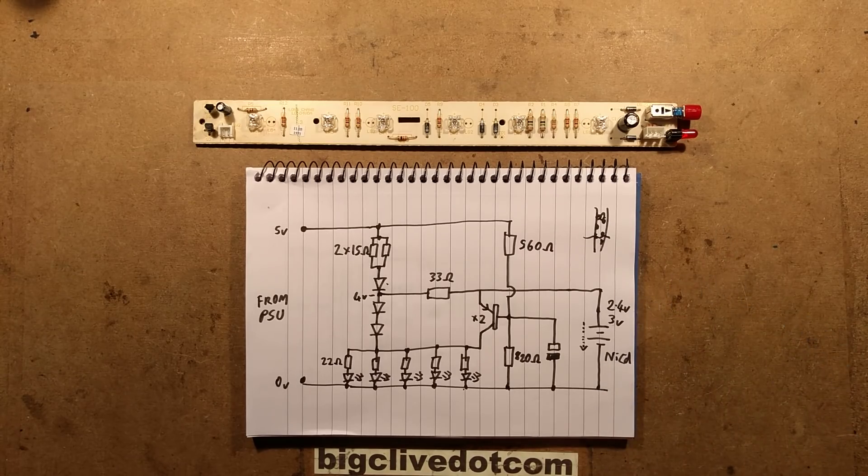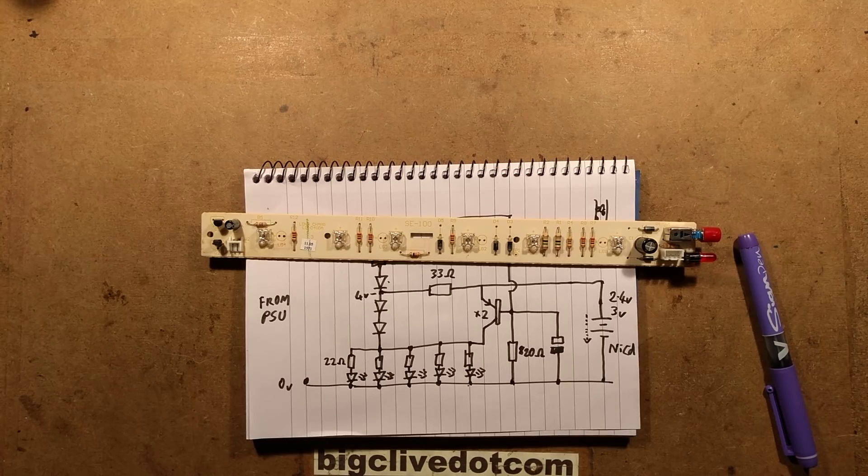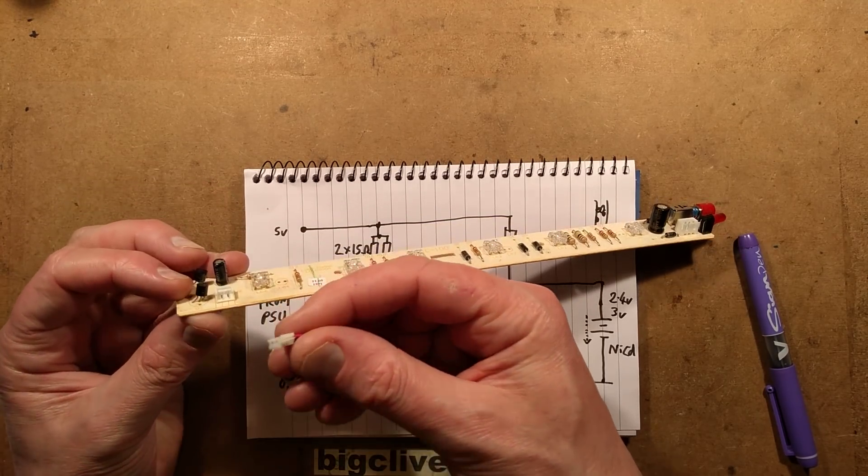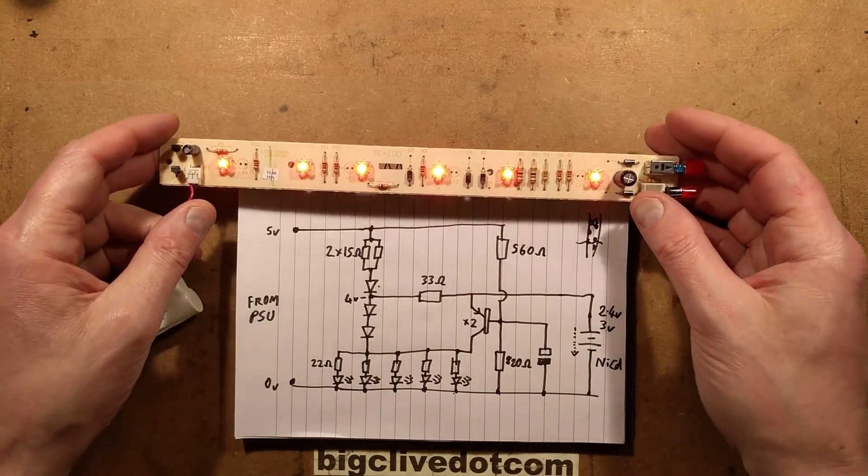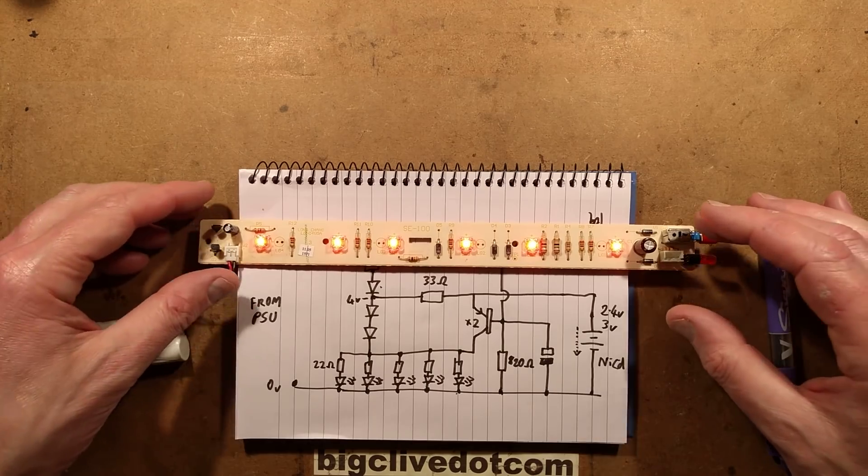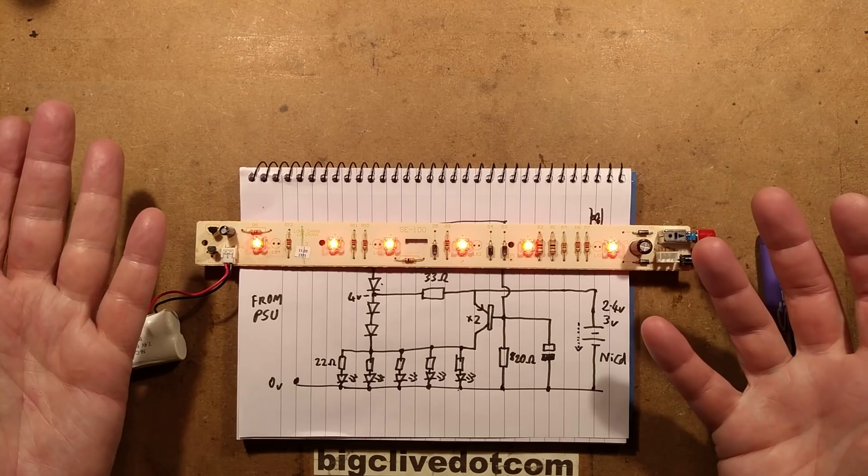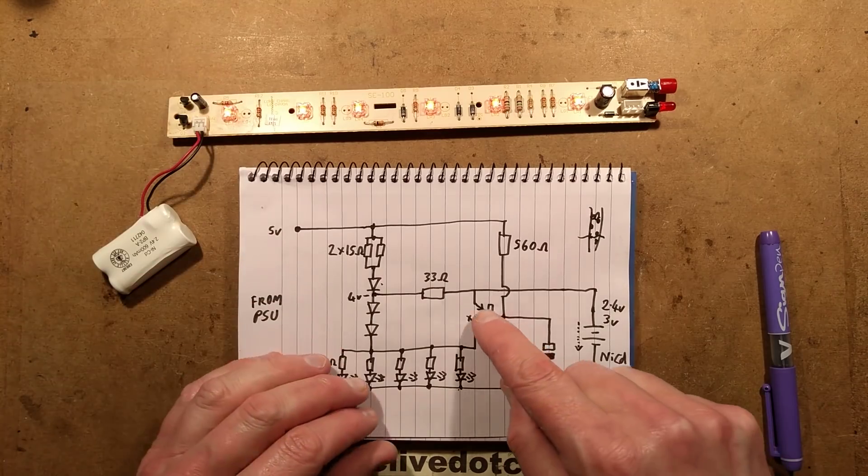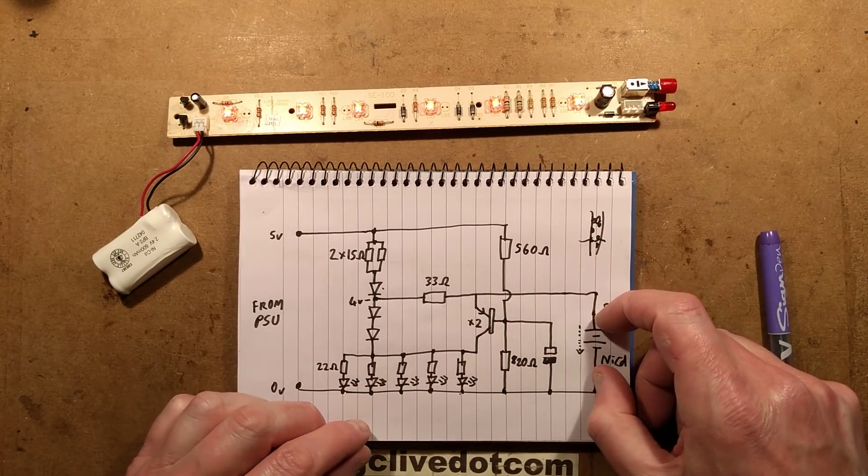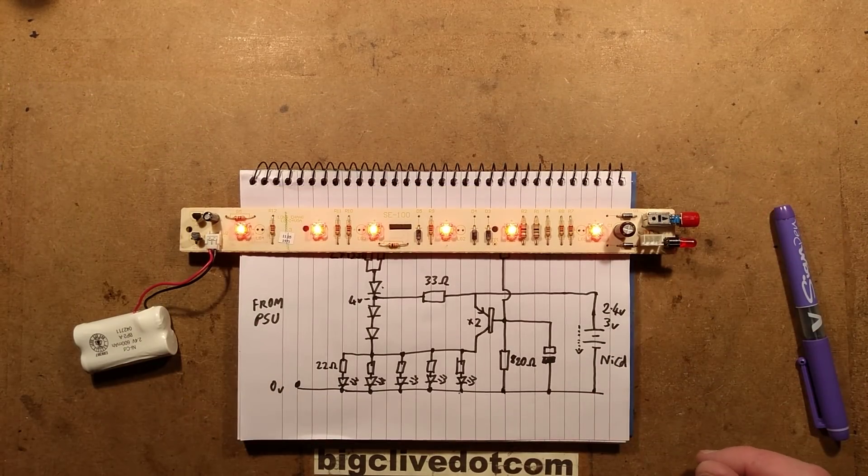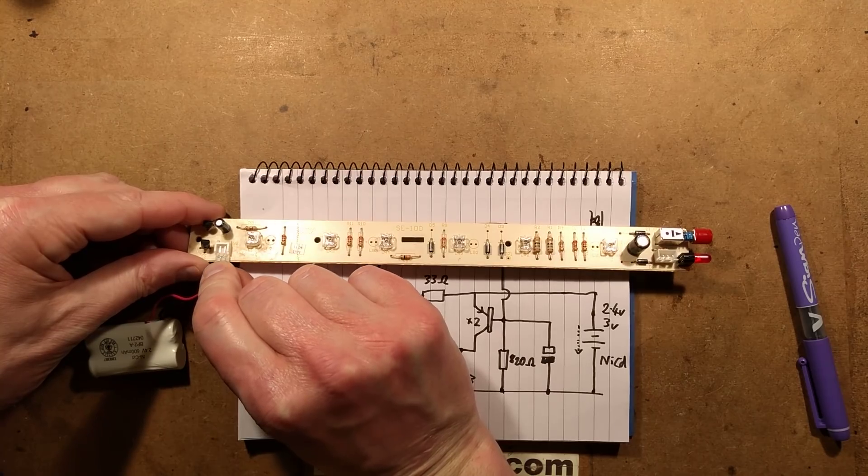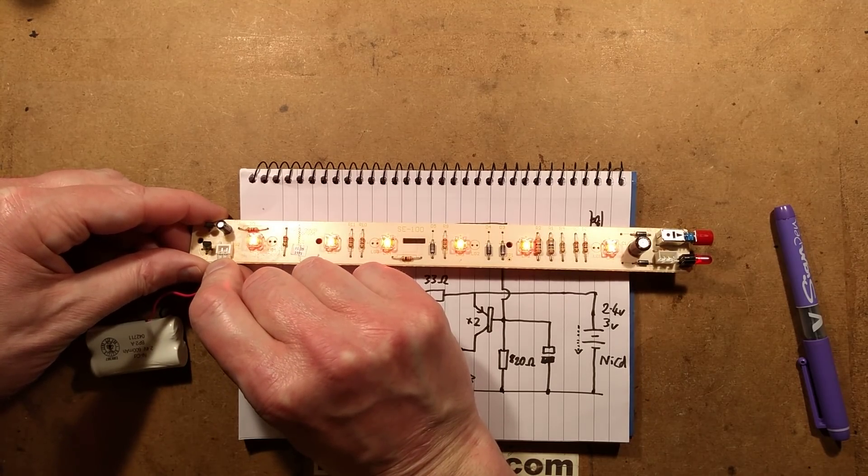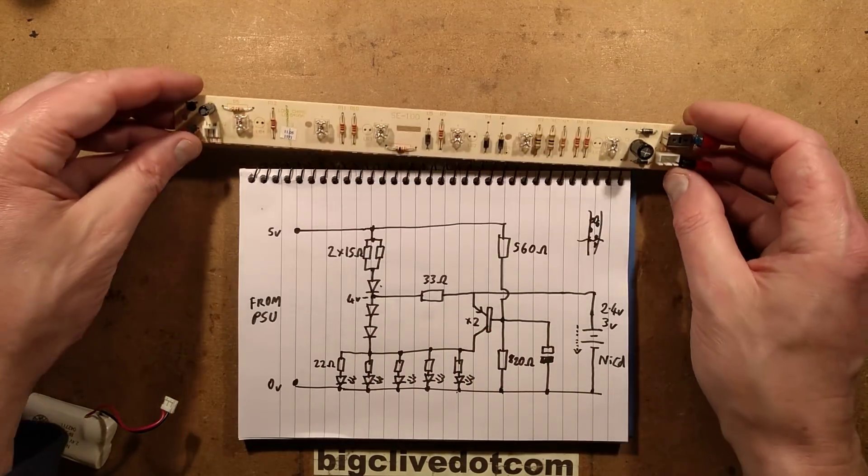The British ones have a feature where if you connect the battery, they won't light. This one lights instantly. The point of that is during installation—with this one, when you connect the battery and close the box, it lights up even though you haven't supplied mains power yet, and would gradually run the LEDs down, fully discharging the cells. Not a terrible issue if power is turned on fairly soon. But in the UK, if I plugged that on they wouldn't light until you turned the mains power on, then they'd light. When you turned power back off, they'd remain lit in emergency mode.